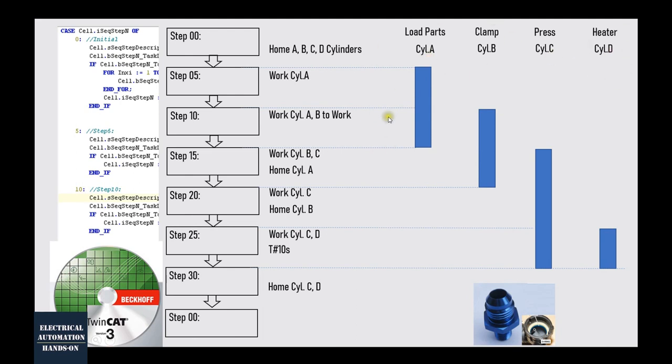Basically, when we program the automatic sequence control, there will be two main parts. The first part is the sequence control. This is a sequence control structure, and in each step we have conditions to move to the next step. Between the steps, we have a timer, so we can control the interval time. And that is the fixed structure. If you need to apply this sequence structure to other applications, you can use a similar structure, copy and paste it, and use a different sequence control structure.